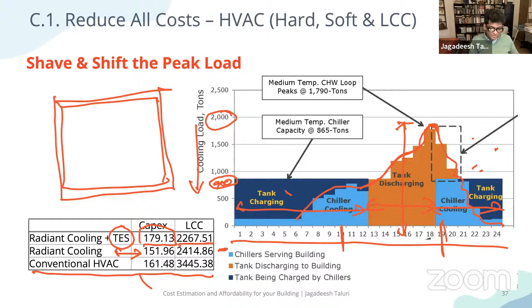But if I look at the life cycle costing, I'll be spending much lesser on energy, even compared to radiant cooling, because during the day I'm not using the chiller when peak electricity charges apply, and during the night when charges are low, that's when I run the chillers the most. So if you do the life cycle costing in this scenario, you'll be surprised, it's much lesser than even the radiant cooling or the conventional building. So if someone is going to build, own, and operate the building, they'll see that even though they're spending more capex than they want, there's merit in it because it leads to substantial savings and also future-proofs the building quite a bit.